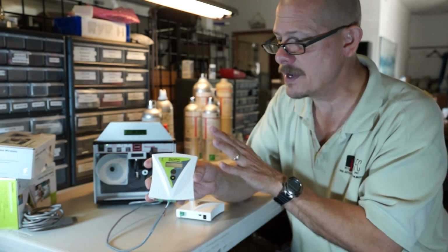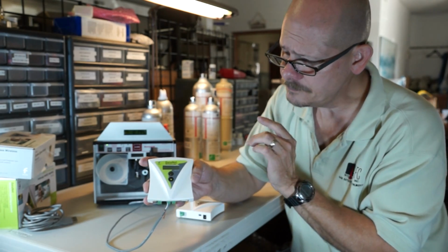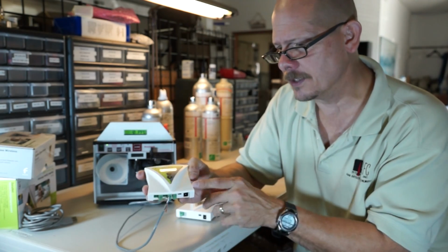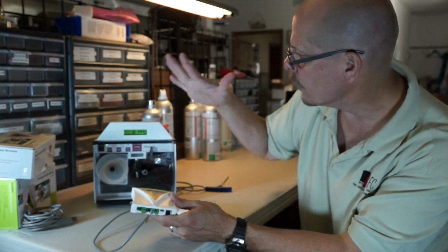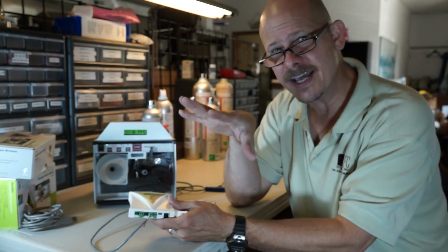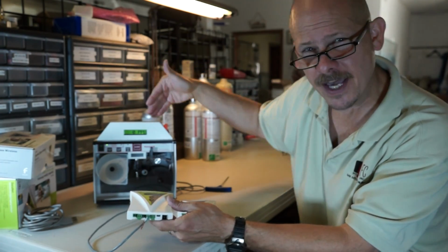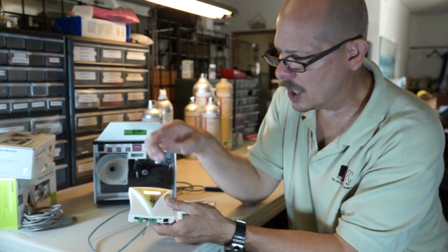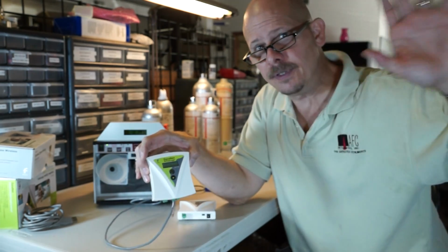So I highly recommend going with a DataNet device that has temperature and humidity. And this particular one is called the DNL 920. Now the 920 series has 4 inputs for 4 individual instruments. So we take 4 different gas fixed monitors or portable monitors, as long as they have that 4 to 20 milliamp output.